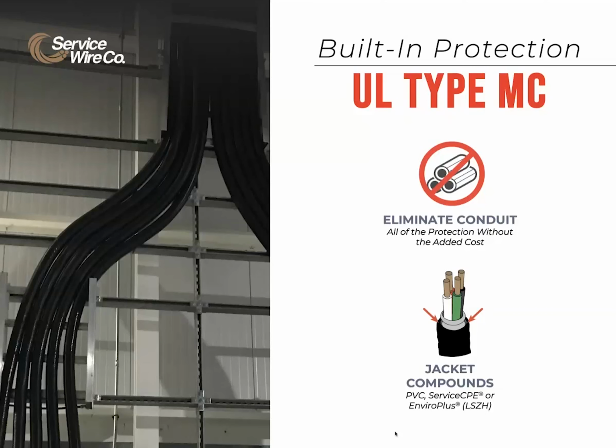3-inch galvanized conduit and wire can take up to 33 hours per 100 feet to install based on NEC recommended labor hours. 3-inch PVC pipe and wire takes about 23 hours. But ServiceWire's 4-aught MC, for example, takes on average 7.5 hours per 100 feet. Contractors who use Type MC armored cable often report between 50 to 70% combined labor and material savings versus traditional pipe and wire jobs.